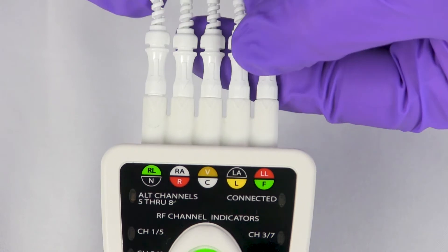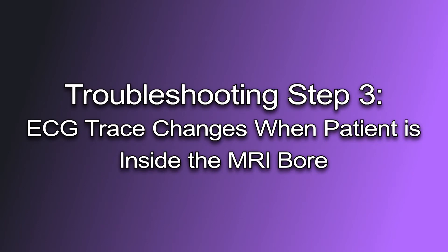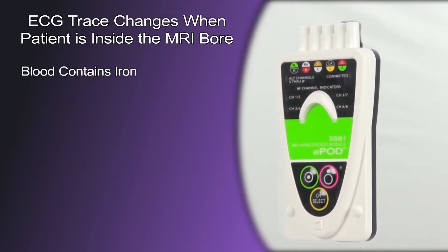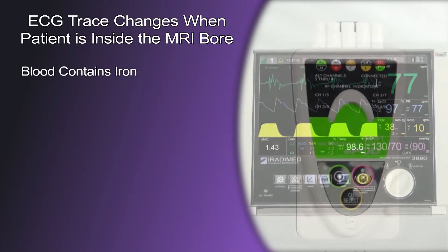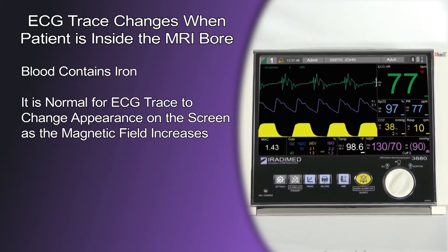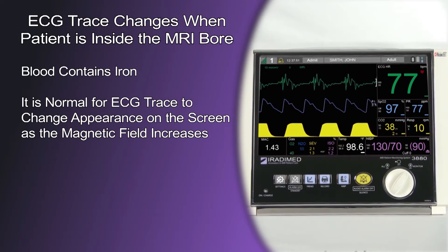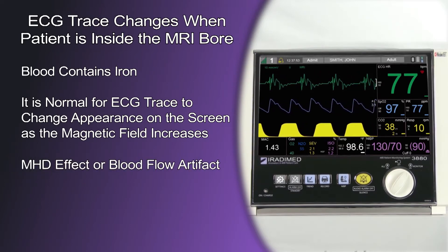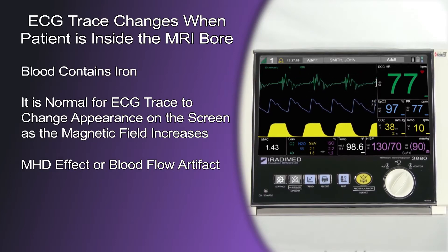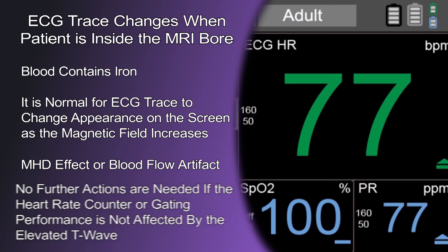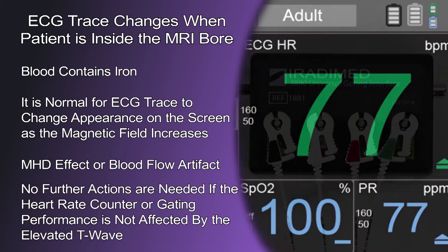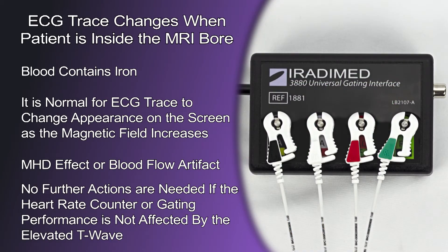Broken lead wires often have an ECG trace with no baseline. Troubleshooting Step 3: ECG trace changes when patient is inside the MRI bore. Blood contains iron and the blood inside the MRI scanner creates a small signal; it is normal for the ECG trace to change appearance on the patient monitor screen as the magnetic field increases. This phenomenon is referred to as the MHD effect or flow artifact. The stronger the magnetic field, the more potential for an elevated T wave. No further actions are needed if the heart rate counter or gating performance is not affected by the elevated T wave.